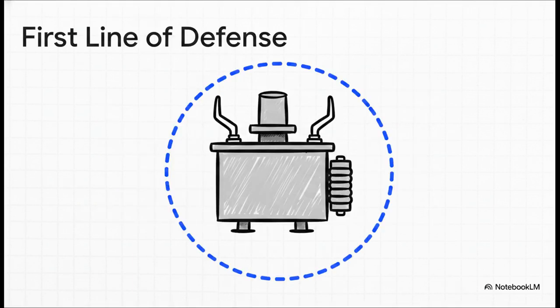We've successfully built a robust first line of defense. We've got our bushings providing safe, insulated exits through the grounded tank. We have arcing horns acting as sacrificial spark gaps, taking the hit so the transformer doesn't have to. We've got surge arresters standing by to precisely clamp massive voltage spikes to ground in a fraction of a second. And of course, our tank selection, choosing between dry type for indoor safety and hermetically sealed for rugged outdoor longevity. Every single one of these components is carefully engineered to protect the vital winding insulation inside, ensuring that a single random lightning strike doesn't plunge an entire neighborhood into darkness.